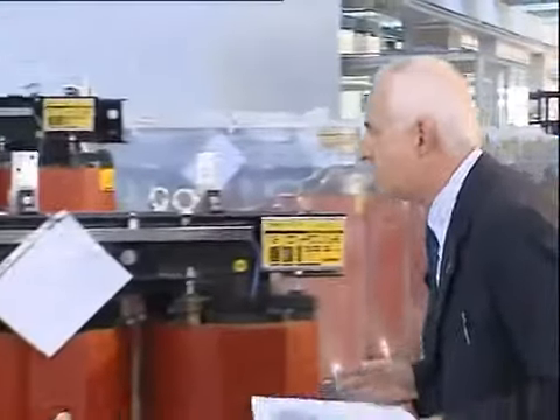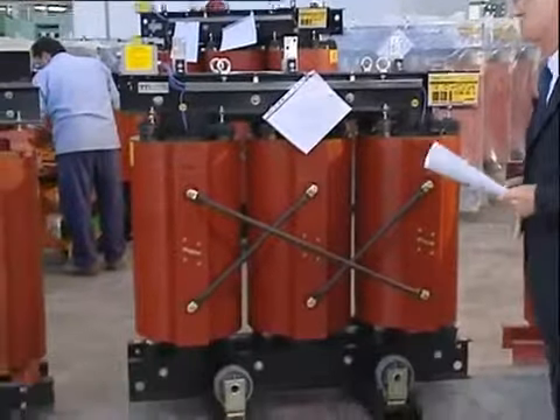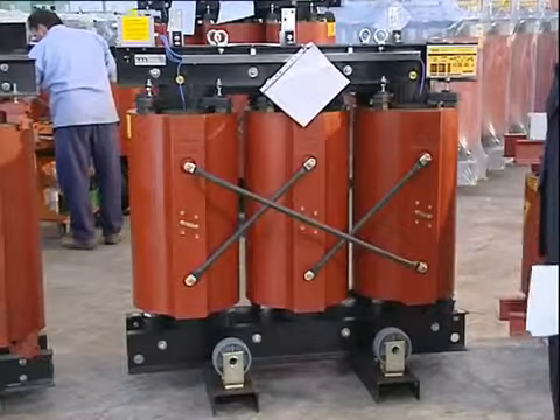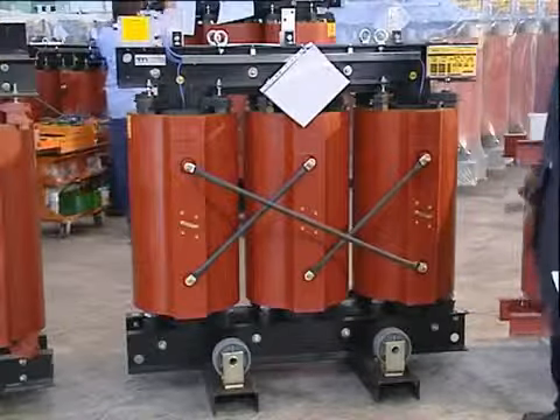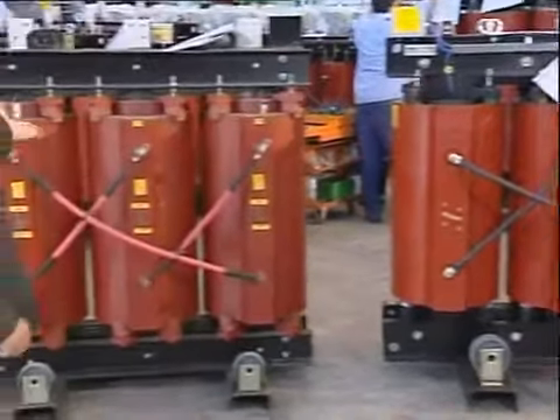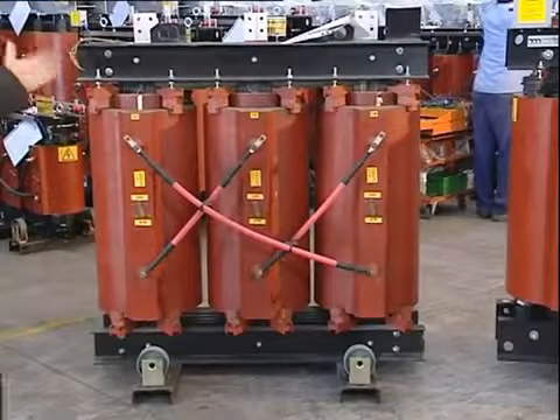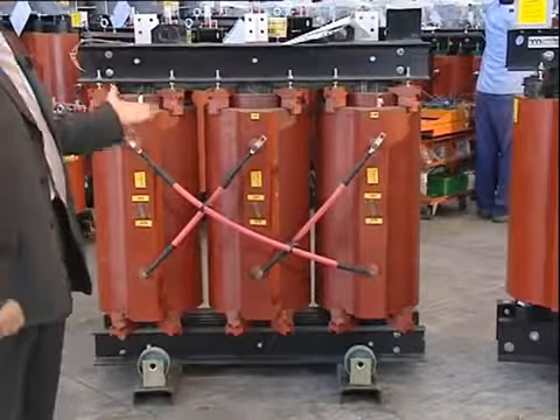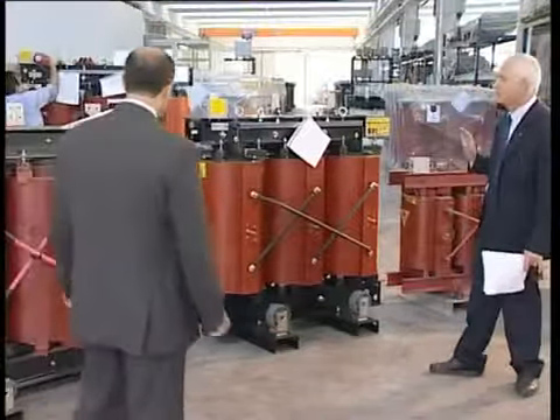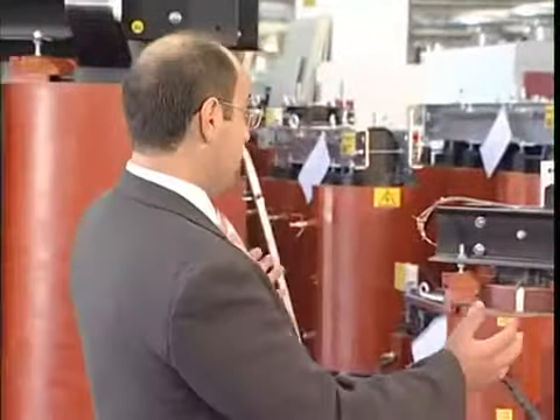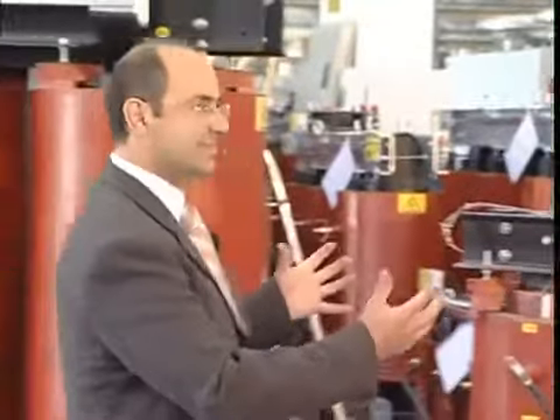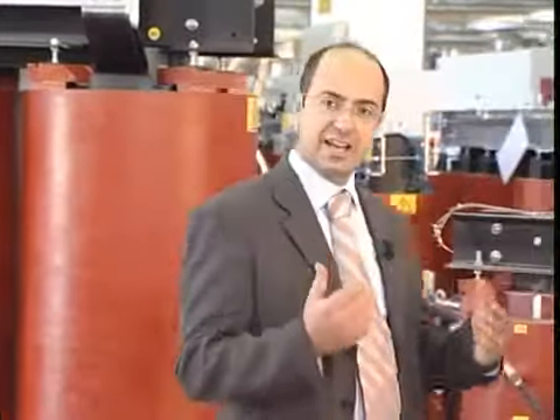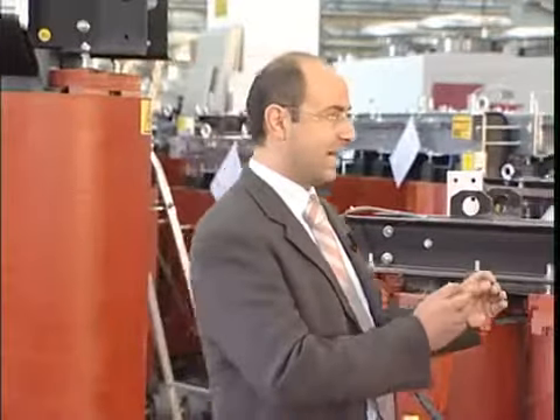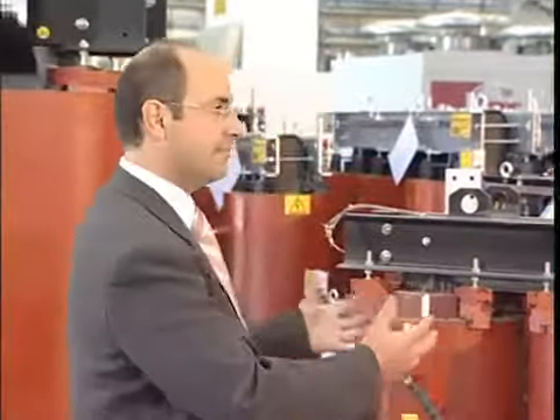Good. I now propose to move toward these two intermediate transformers. What are they, Franco? Here we have two medium power transformers. Meaning 630 kilovolt amperes. This is our product, while the other one has been manufactured by one of our competitors and has a rated power of 800 kilovolt amperes. Let me understand correctly, these transformers look the same to me. Yes, I must say that in terms of shape, by and large, there are no big differences. However, I would like to focus our attention on the details we are interested in, rather than discussing the actual rated value of these pieces of equipment.